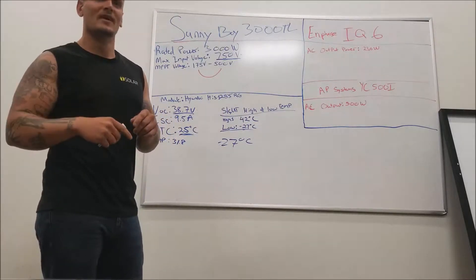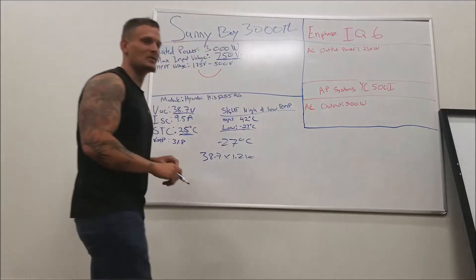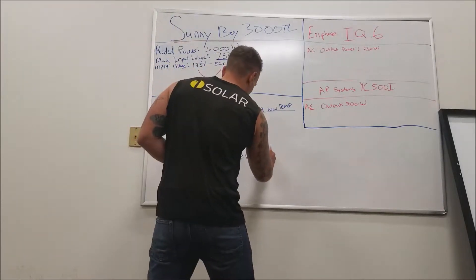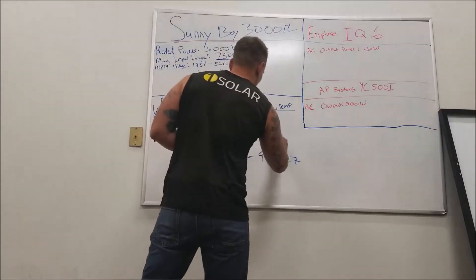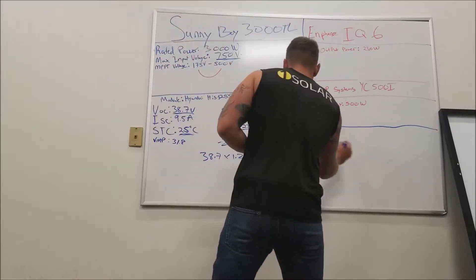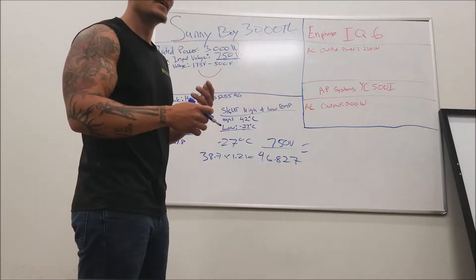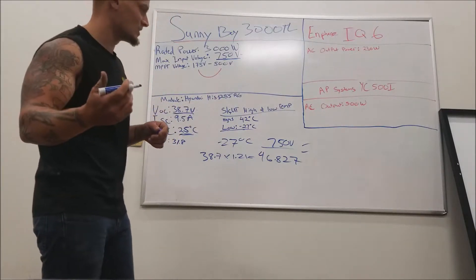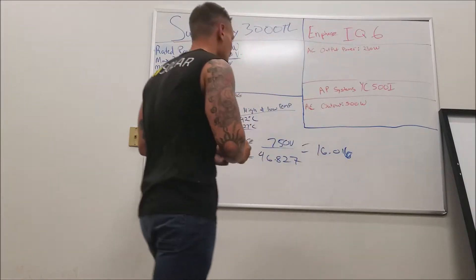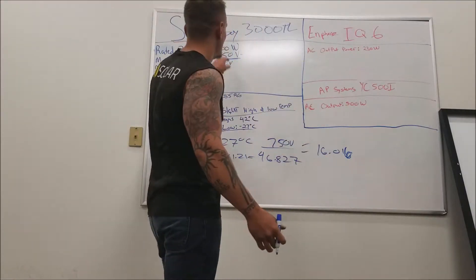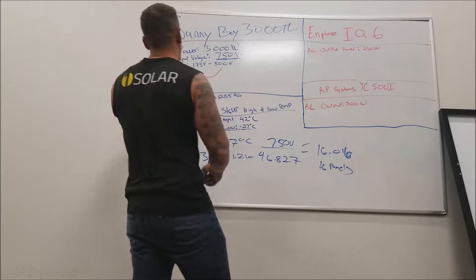At negative 27, the correction factor is 1.21. So 38.7 times 1.21 equals 46.827 volts. We take 750 volts and divide by 46.827. 750 divided by 46.827 equals 16.016. We can't round up because that puts us over 750 volts, so that's 16 panels per string for this inverter.